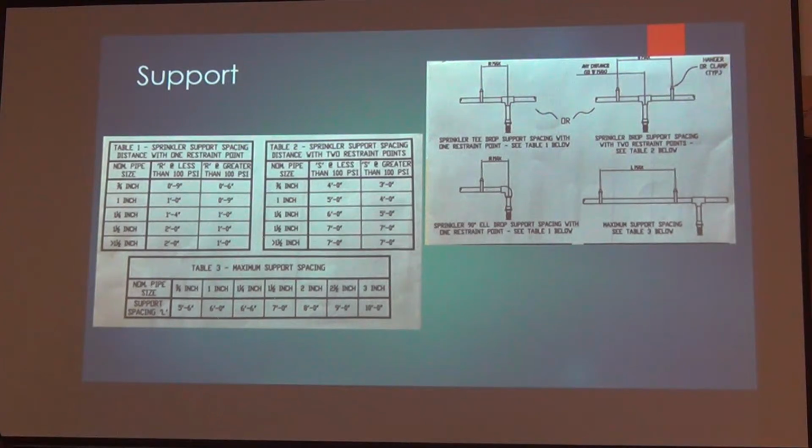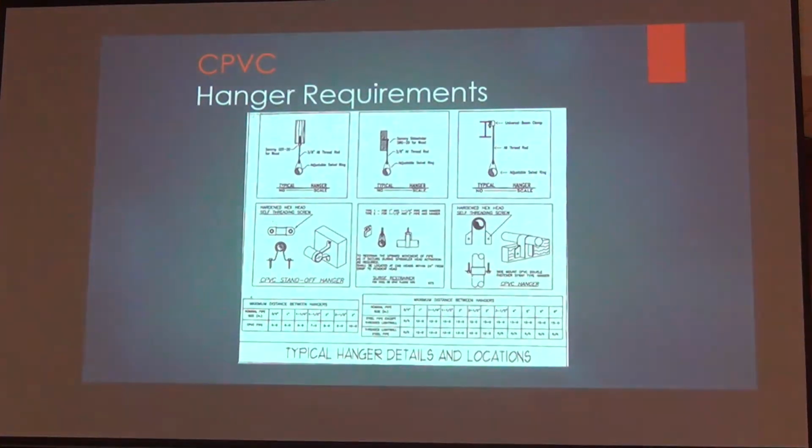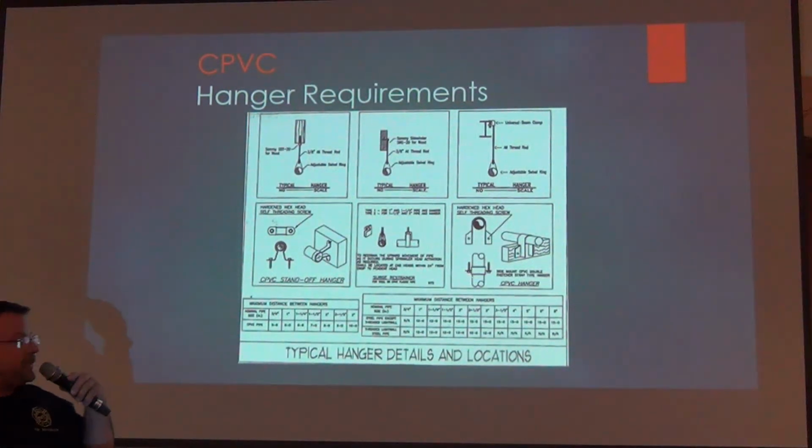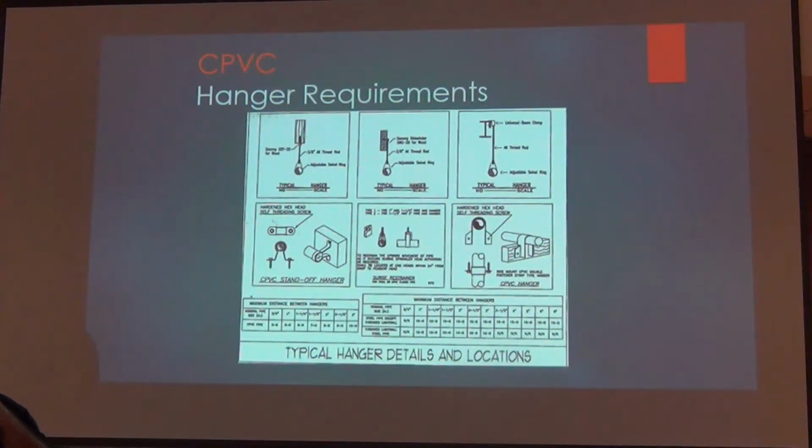All right, so not gonna get into the minutiae of that too much, but there are specialty clamps that you can use on Blaze Master. Okay, they're all different types. They should be listed on the plan as to how they should be secured. They must be secured. Every sprinkler drop must have less than 1/8 of an inch of movement. And this is a 13 system requirement. If you have an inspection on a 13 system with a pump, every hanger must have surge suppression on it. Because once the pump kicks in, it pumps up the pipe and it makes it move.